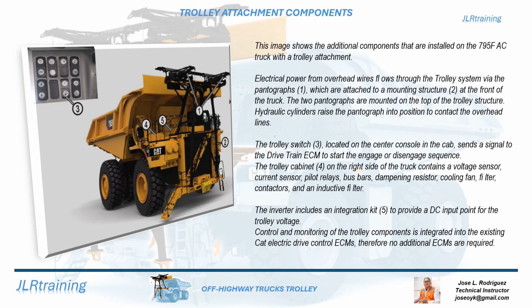The trolley switch, 3, located on the center console in the cab, sends a signal to the drivetrain ECM to start the engage or disengage sequence. The trolley cabinet, 4, on the right side of the truck contains a voltage sensor, current sensor, pilot relays, bus bars, dampening resistor, cooling fan, filter, contactors, and an inductive filter. The inverter includes an integration kit, 5, to provide a DC input point for the trolley voltage. Control and monitoring of the trolley components is integrated into the existing CAT electric drive control ECMs, therefore no additional ECMs are required.